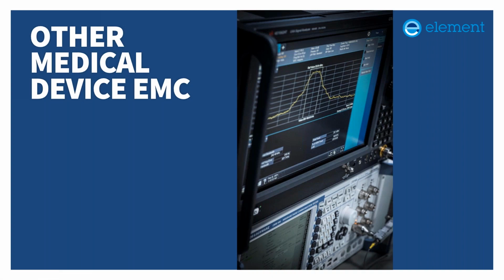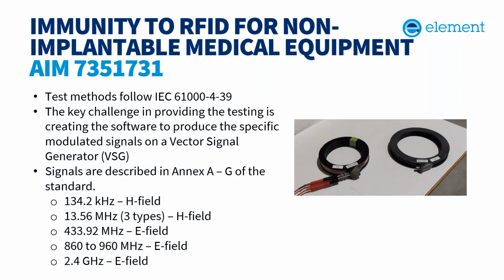So another aspect for medical device EMC is the AIM 7351731. It's a susceptibility test method for immunity to RFID signals. So it covers both H field and E fields for RFID frequencies. And obviously, people in the medical device field are aware, RFID is everywhere. Clinics, hospitals, home. It is being used to track just about everything. And so this was a test method developed by AIM to address that risk.